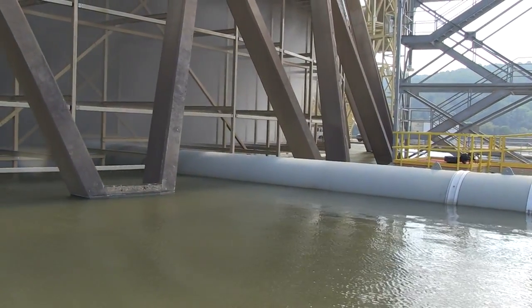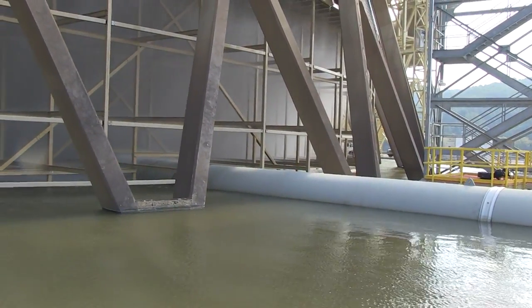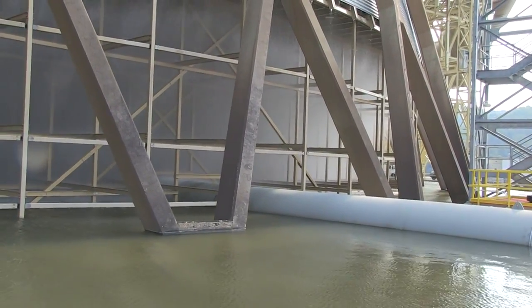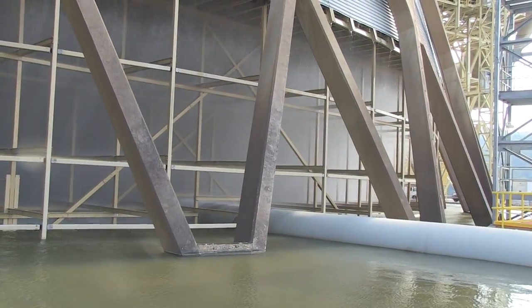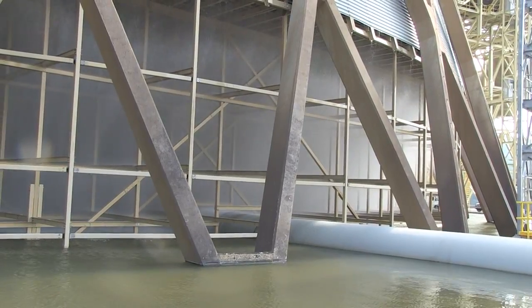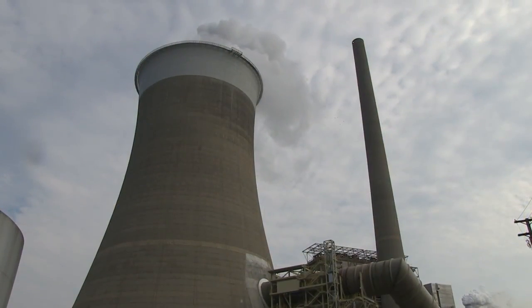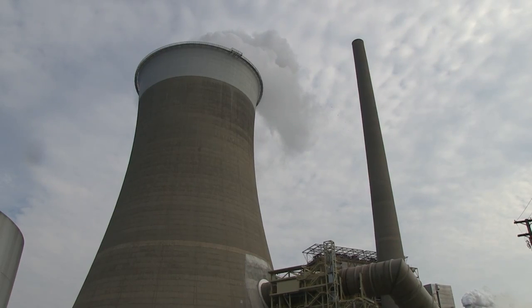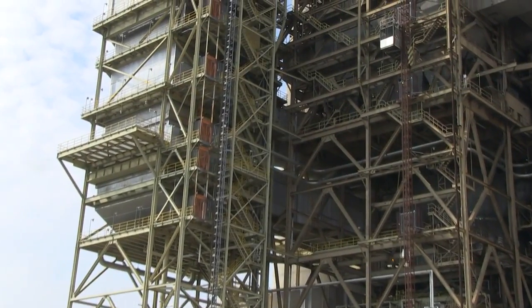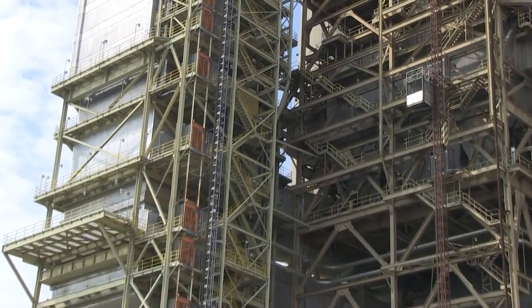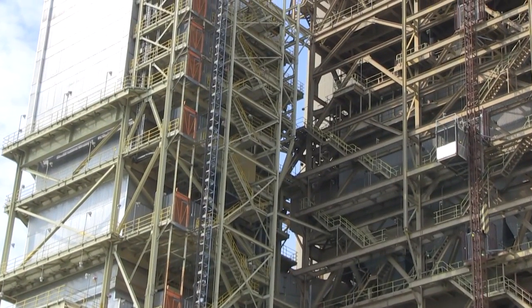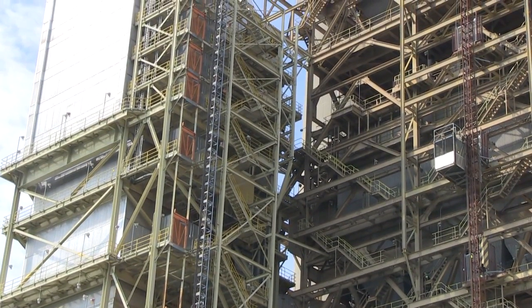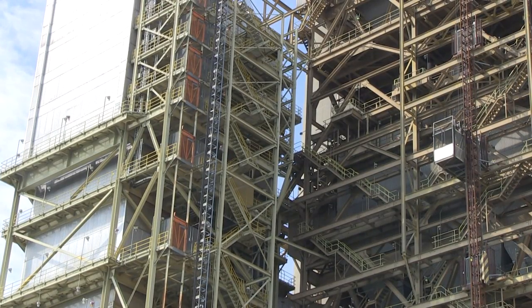The hyperbolic shape of Unit 3's 423-foot cooling tower creates a natural draft as more than 300,000 gallons of water per minute circulate, dropping the temperatures of the condenser water by 20 degrees. The small amount of water lost through evaporation out of the top of the cooling tower is replenished from the Ohio River. While the cooling systems handle the heat, special equipment is cleaning the hot air coming out of the boilers. About 14% of the coal that is burned inside the boiler is not consumed.